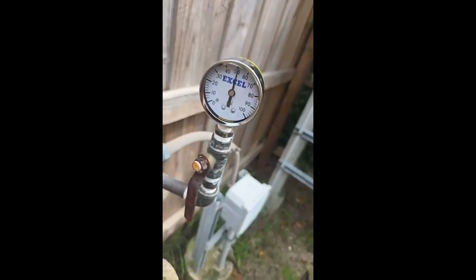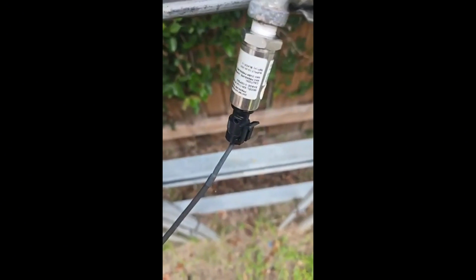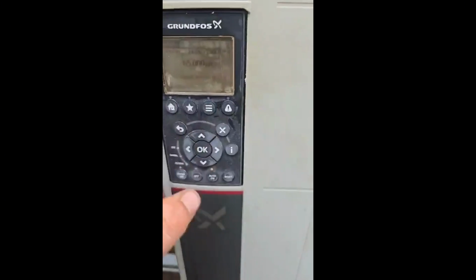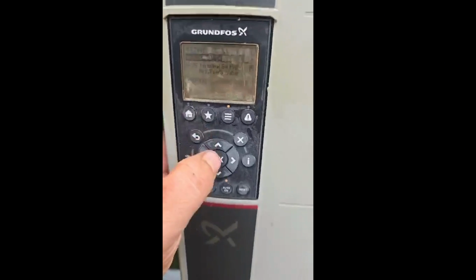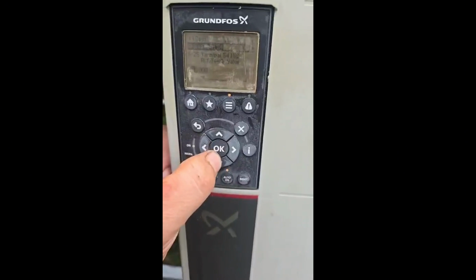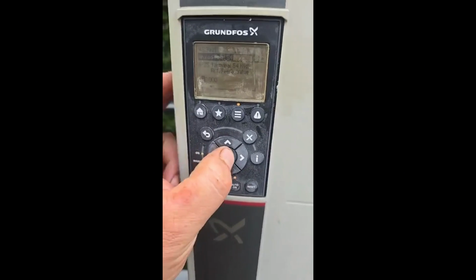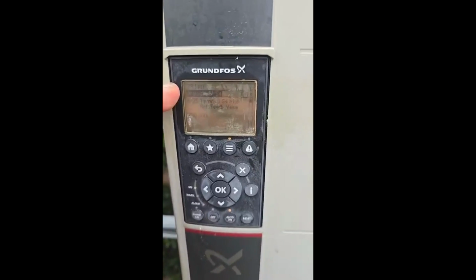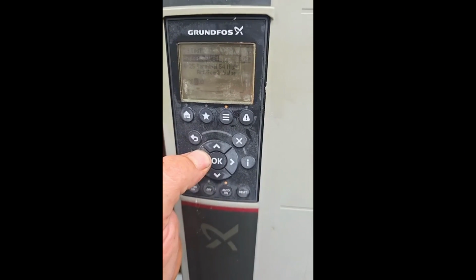Okay, got it running. 50 psi. 50 psi. Everything's lining up. It's got a transducer here. Range 0 to 150, 4 to 20 milliamp. Boom, 150. See that 49.2 psi? When we came here, this was set to 120 like the factory transducer. See how it's 39.1 now? So the scaling was off on this. It was reading low pressure.